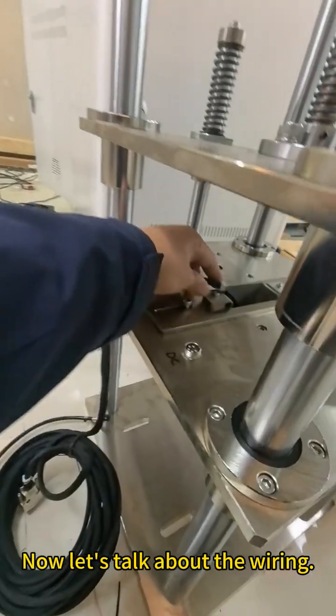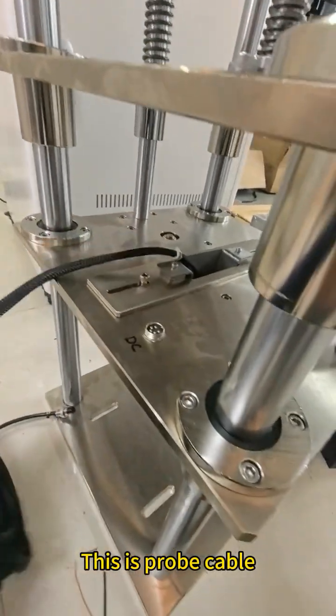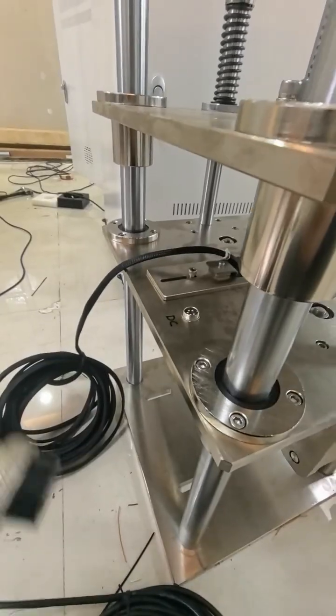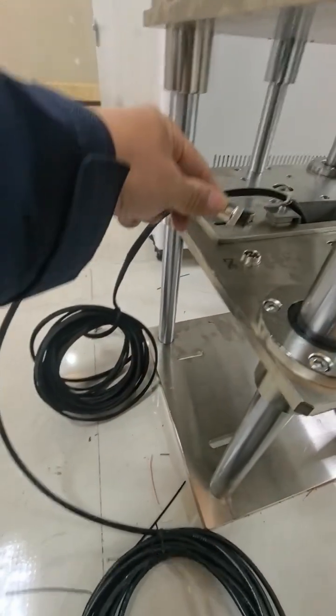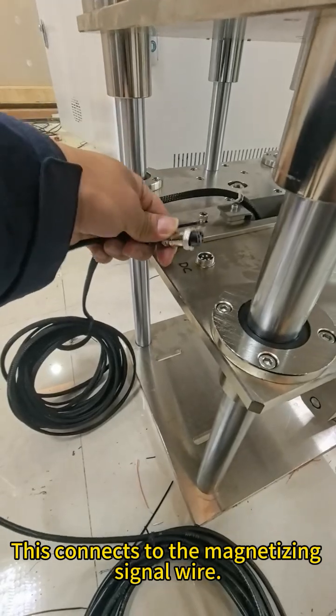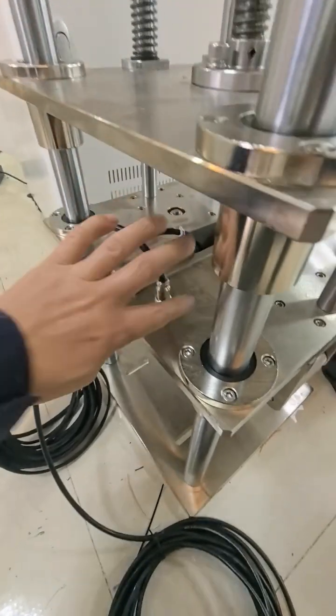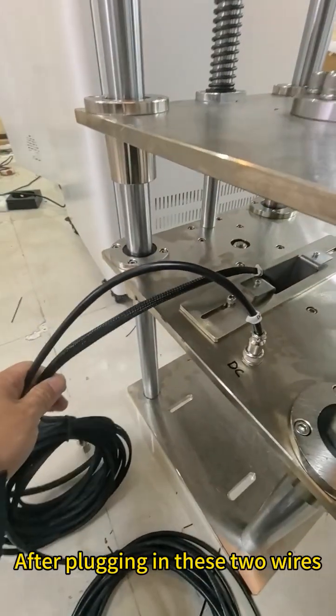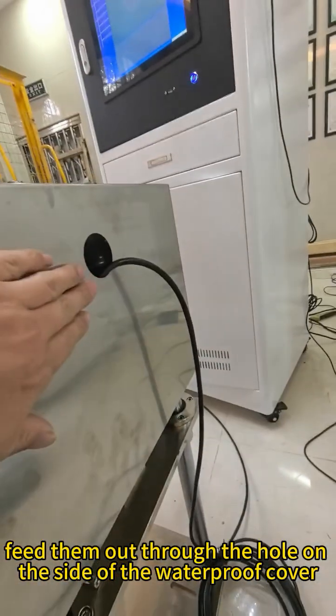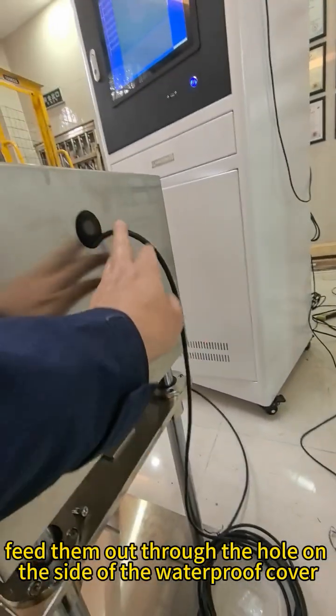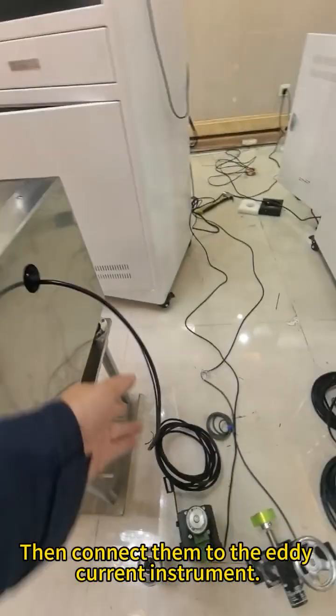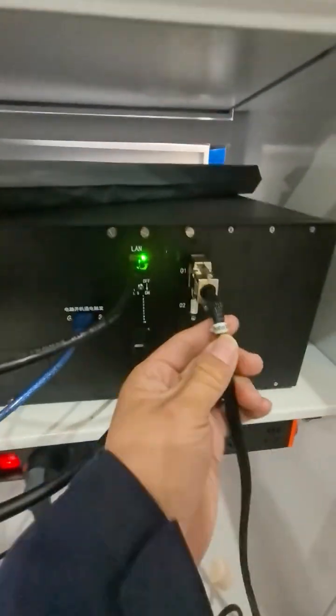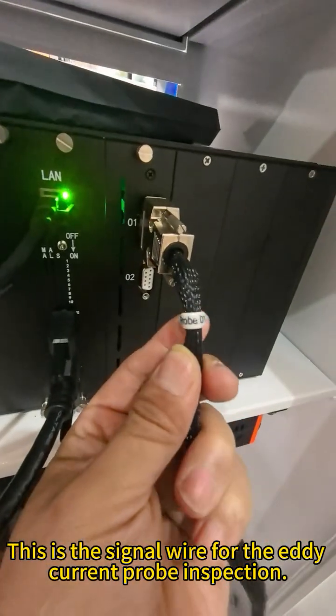Now let's talk about the wiring. This is the probe cable. It's marked with DC. This connects to the magnetizing signal wire. After plugging in these two wires, feed them out through the hole on the side of the waterproof cover. Then connect them to the eddy current instrument. This is the signal wire for the eddy current probe inspection.